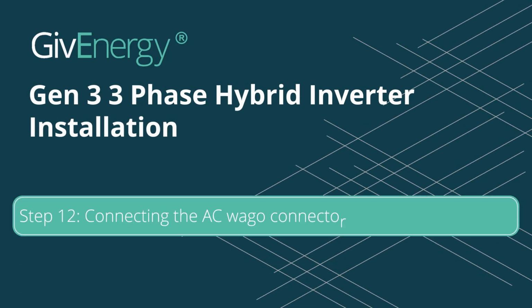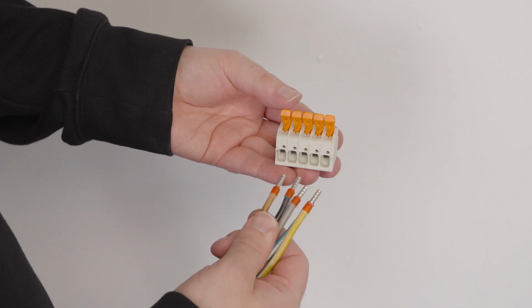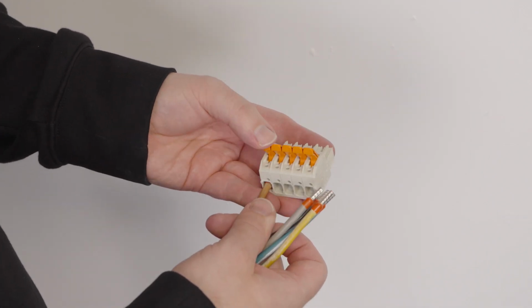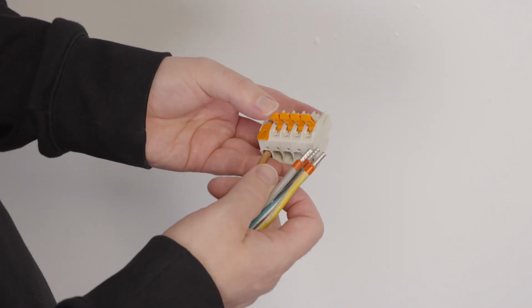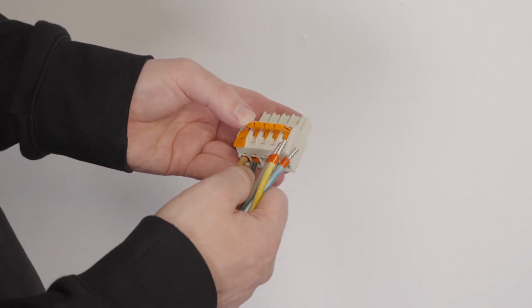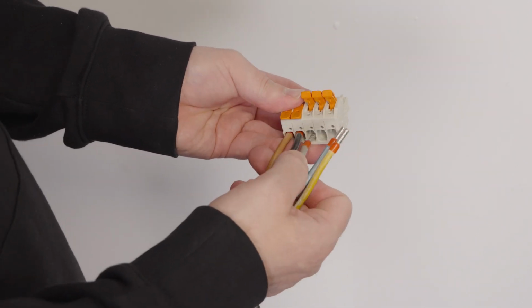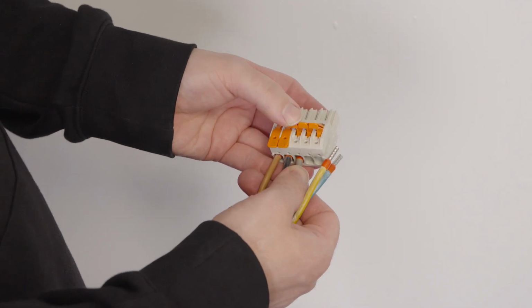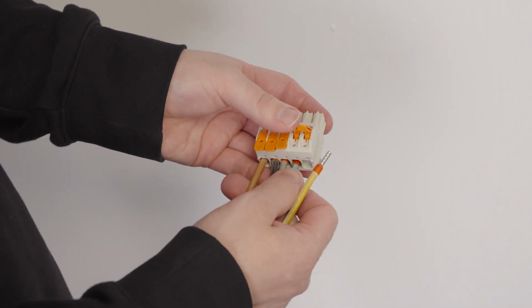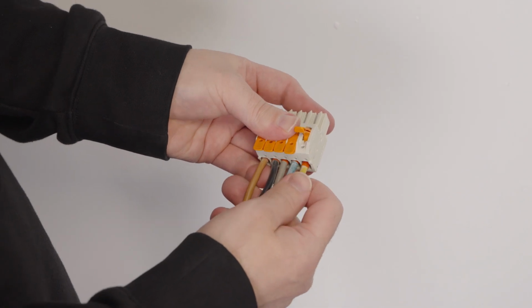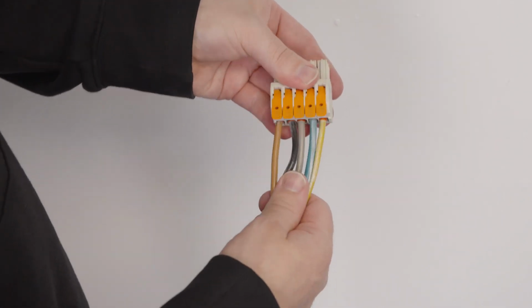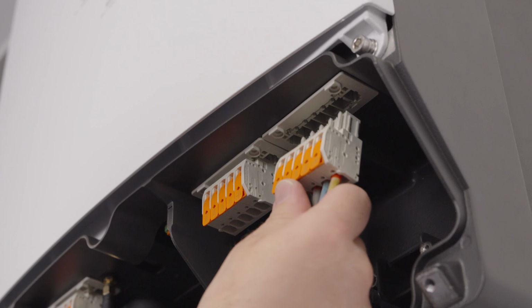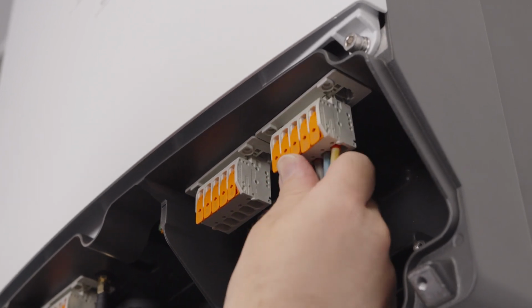Step 12. Connecting the AC Wago connector. In the UK, brown goes to L1, black to L2, grey to L3, blue to neutral, and lastly earth to earth. Firmly connect the cables into their respective ports, clicking the lever arch levers down. Ensure that the Wago terminal is firmly plugged into the inverter.